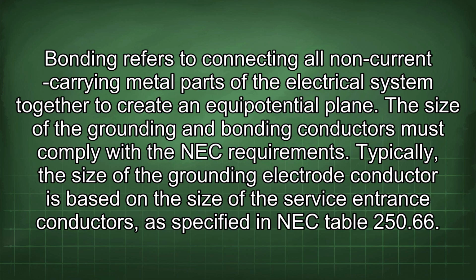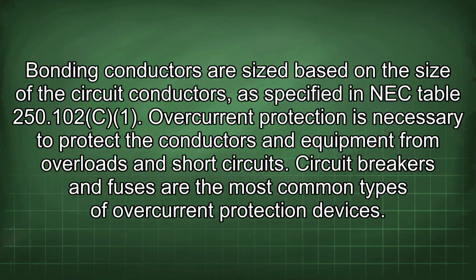The size of the grounding and bonding conductors must comply with the NEC requirements. Typically, the size of the grounding electrode conductor is based on the size of the service entrance conductors, as specified in NEC Table 250.66. Bonding conductors are sized based on the size of the circuit conductors, as specified in NEC Table 250.102.